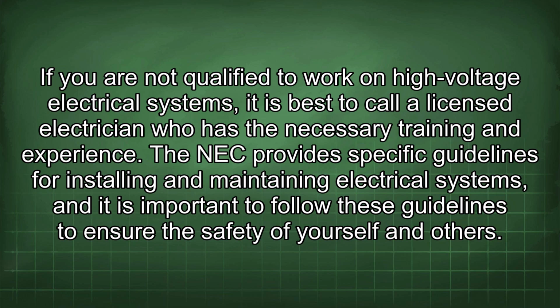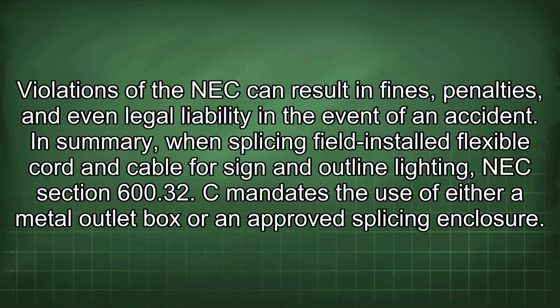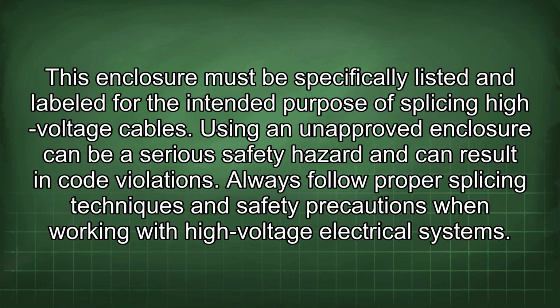The NEC provides specific guidelines for installing and maintaining electrical systems, and it is important to follow these guidelines to ensure the safety of yourself and others. Violations of the NEC can result in fines, penalties, and even legal liability in the event of an accident. In summary, when splicing field-installed flexible cord and cable for sign and outline lighting, NEC Section 600.32 C mandates the use of either a metal outlet box or an approved splicing enclosure. This enclosure must be specifically listed and labeled for the intended purpose of splicing high-voltage cables. Using an unapproved enclosure can be a serious safety hazard and can result in code violations. Always follow proper splicing techniques and safety precautions when working with high-voltage electrical systems.